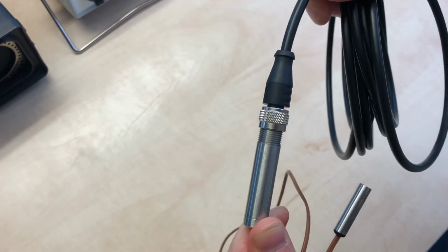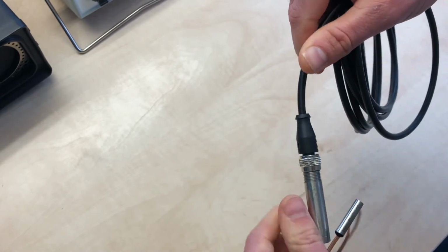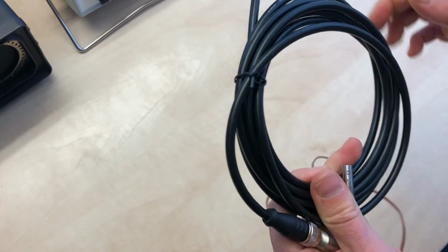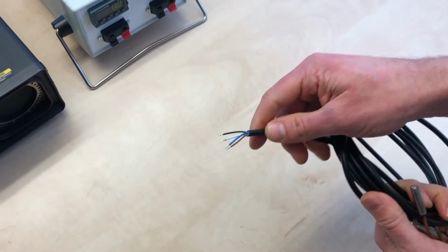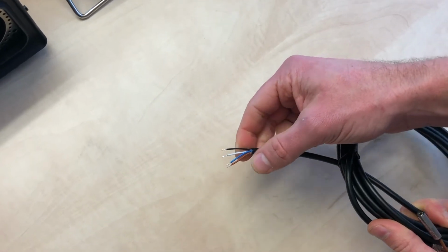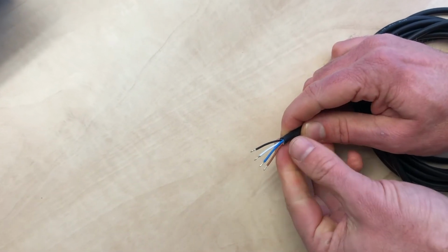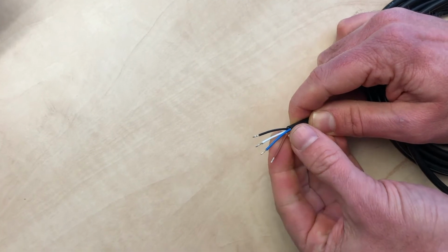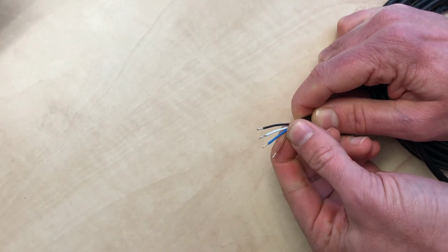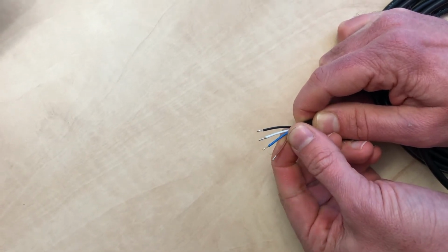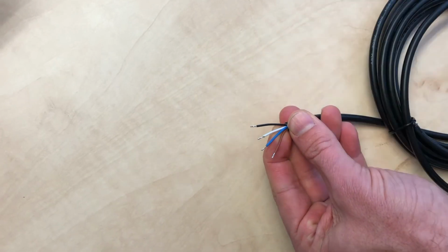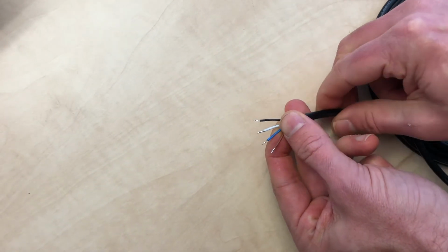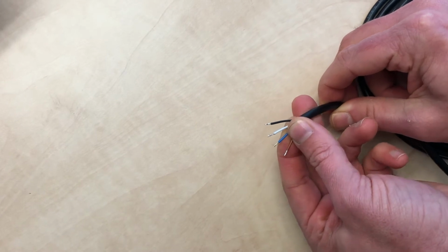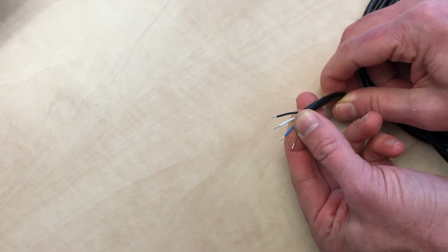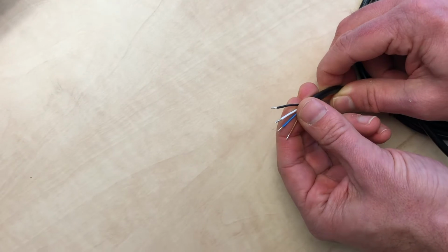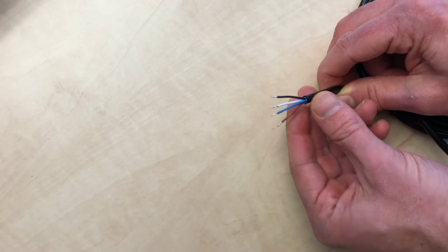Like this, very solid, very reliable. In principle, you can order any cable length that you desire. At the end of the cable are 4 wires. The brown wire is the power supply, 12 to 28 volts. The blue wire is the ground. The white wire is the voltage output, and the black wire is the current signal output.